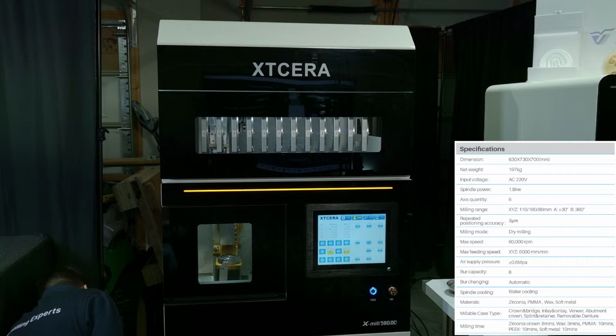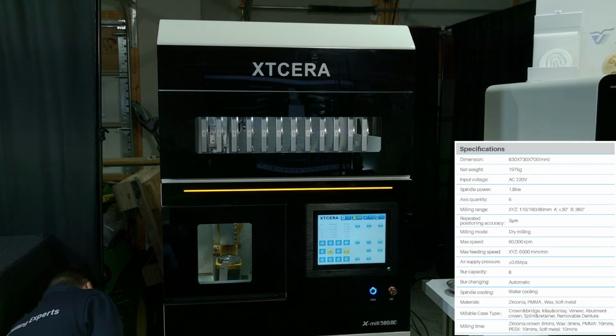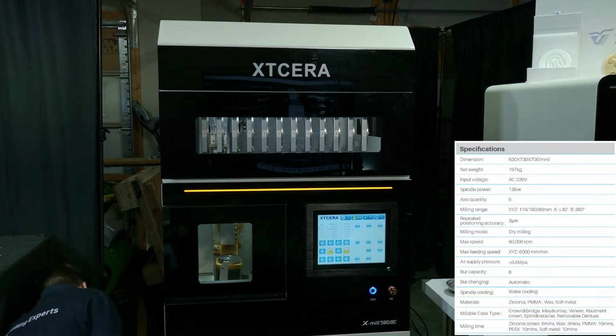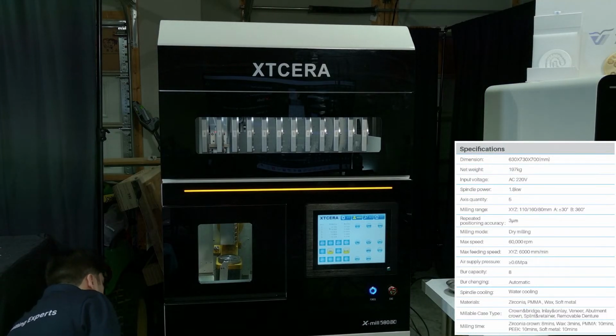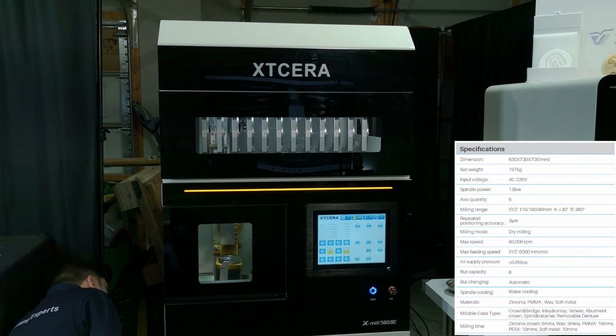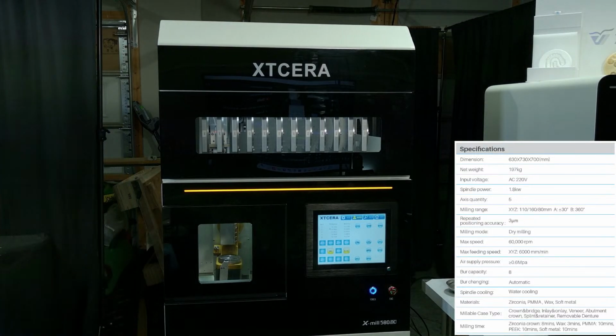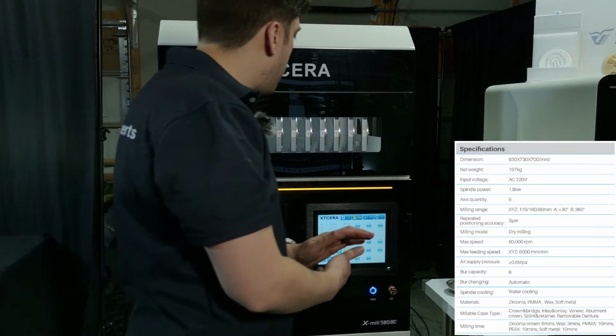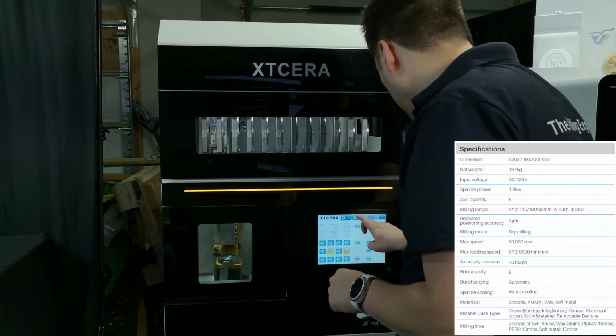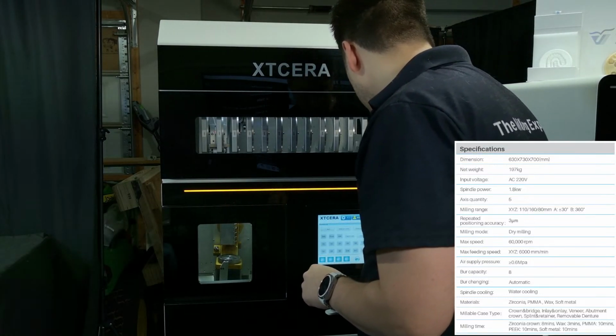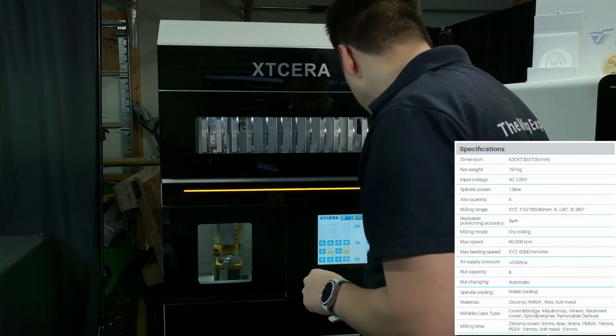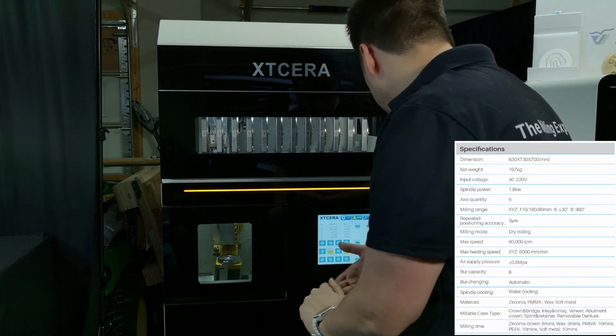Okay, looks like I'm capping out at 0.58. So I think this is more an issue with my compressor. I'm going to have to adjust the top end of it and make sure that it's maintaining 0.6. We can give it a go and see how it goes. I think that if we drop below 0.6, we're probably going to have an issue, but let's see what we can work with here. All right, we're going to go into our automatic bur changer. That looks good there.